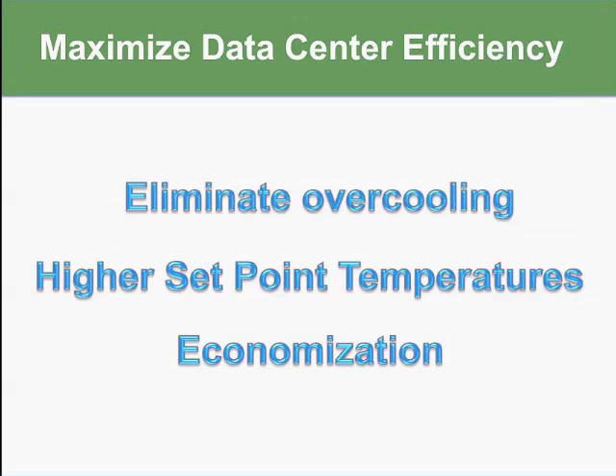So some of the ways to maximize data center efficiency through the exact same airflow management implementations is you're going to eliminate overcooling. As we saw in that one heat map where you're overcooling one side of the room and you're undercooling other sides of the room, your ongoing dynamic control is going to keep that even temperature set point. So you're minimizing your energy usage while providing optimal cooling. As I mentioned before, you can also play with higher set point temperatures. The ASHRAE standards now say that we can get into the 80, 85, even 90 degree set point temperatures for equipment. The important thing, though, is to make sure you're at a consistent temperature. It's the vacillation of those temperatures that really causes harm and risk to the equipment.